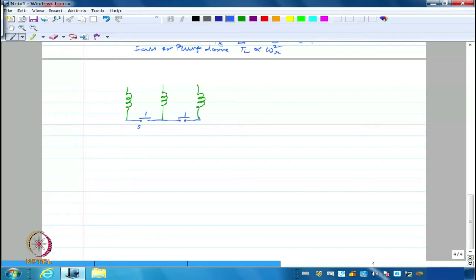These are the starting contactors. They will be closed, and I'm going to have the A, B, C three-phase supply applied here. Right? So this will be the starting contactor which will be closed. And if I want this to be connected in delta, I will have something like this. From here, I will have one contactor. So this will be during running. Right? One more I should have like this.